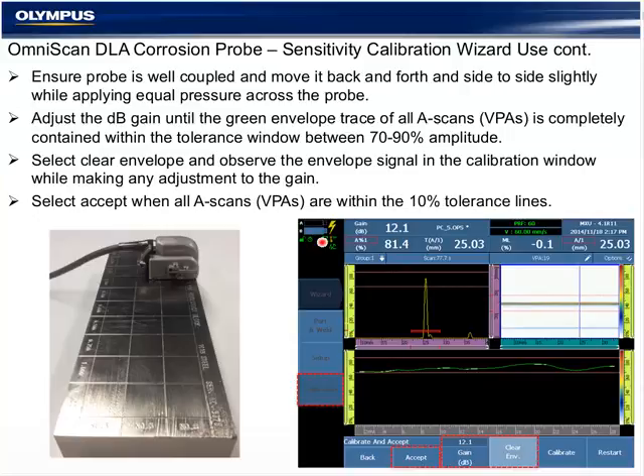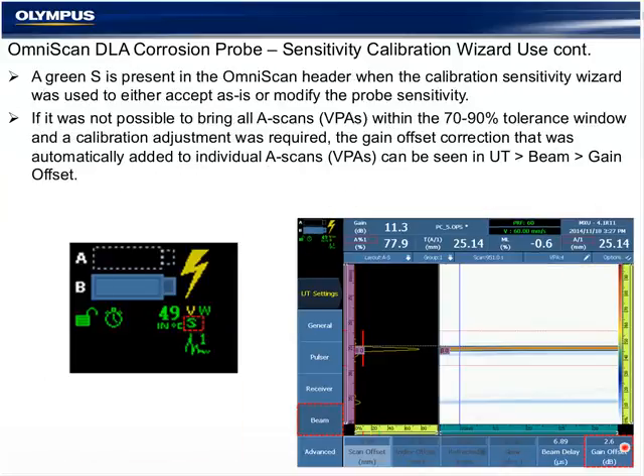For the overwhelming majority of users of this probe are going to be entry-level phased array in most cases with an SX, so the complexity of the setup and understanding of all the functions isn't necessary to be able to perform at a high level with this limited application. And again, an S as a requirement of having validated the sensitivity is a common procedural step we see in many procedures. The point I'm trying to make is you don't actually have to modify the sensitivity like in a weld inspection to be able to validate it.